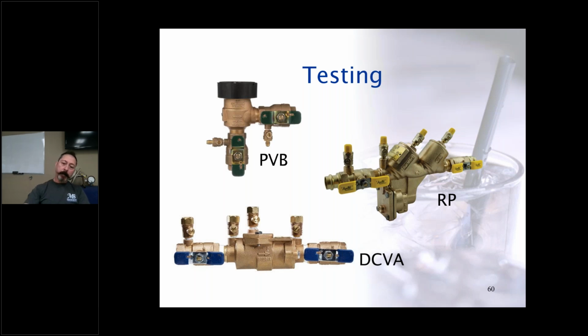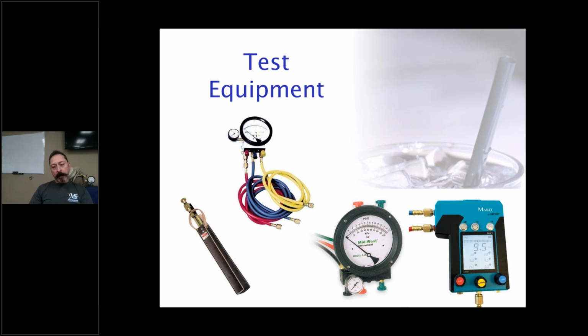These devices, the RP and the DCVA, can actually get up to 10 inches in size. I mean, these things can be massive. Pressure vacuum breakers, or PVBs, tend to be up to the 2-inch range, but they will all be shipped with shutoffs and these test ports to connect your test gauge. This is the type of test equipment that a certified tester will come out with to test the functionality of the backflow preventers, to ensure that those check valves, shutoffs, and everything are working appropriately.